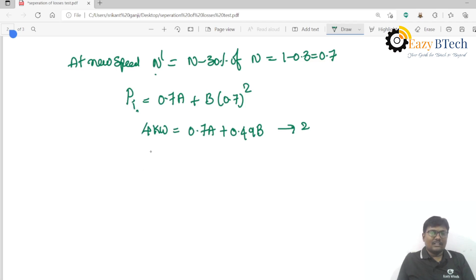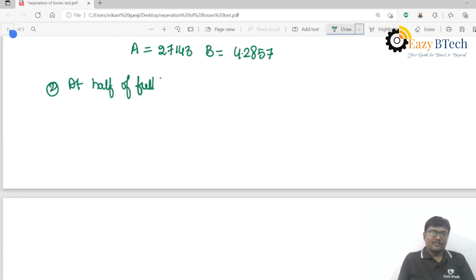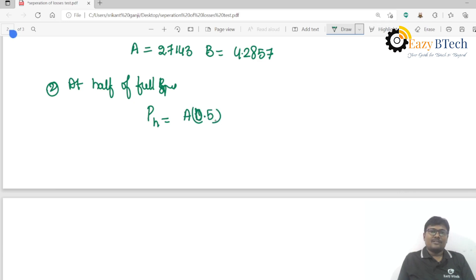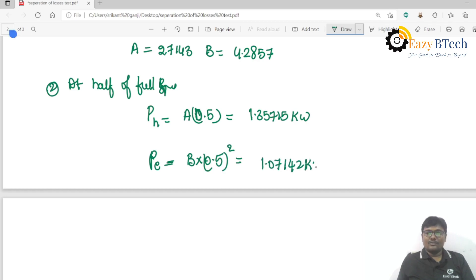Solving these two equations gives a = 2.7143 and b = 4.2857. At half of full speed (N = 0.5): hysteresis loss equals 0.5 × a = 1.35715 kilowatts, and eddy current loss equals b × (0.5)² = 0.25b = 1.07142 kilowatts. This completes the separation of no-load losses test example.